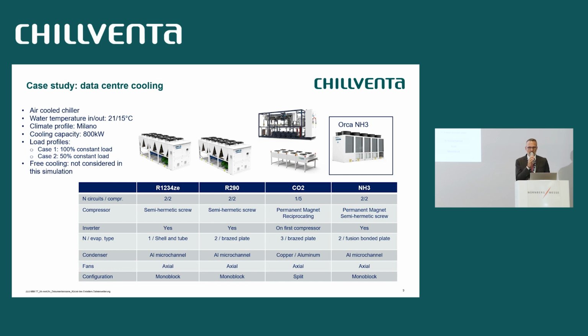So we compare all natural refrigerants and one synthetic refrigerant. And by the way, we have no conflict of interest because in our portfolio, we have all these products. So we are proud to be able to recommend to our customers always the best product for the application. In this case, we considered air-cooled chillers with 1234ZE, with R-290 propane, with CO2, and with ammonia. For CO2, it was a split system. For all of them, we had a semi-hermetic screw compressor, except for CO2, it was a permanent magnet reciprocating compressor.